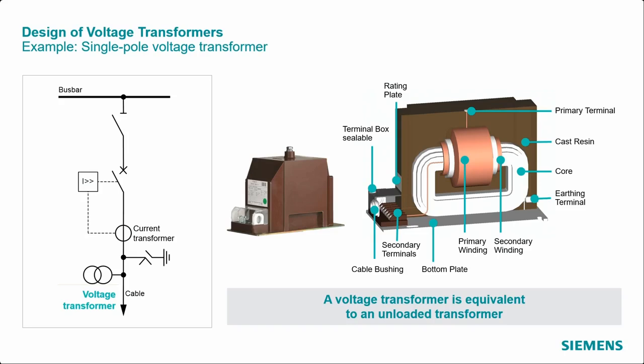The primary winding is designed to handle the high voltage from the power system and typically consists of a larger number of turns of wire. This component is crucial for the step-down of voltage. In single-pole VTs, the primary winding is connected across just one phase and the ground or neutral, in contrast to multi-pole VTs, which can handle multiple phases. The secondary winding serves to step down the high primary voltage seen on the primary winding. The number of turns and wire cross-section are carefully calculated to achieve the desired voltage transformation ratio.